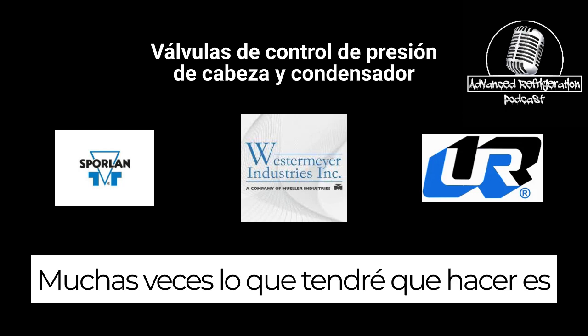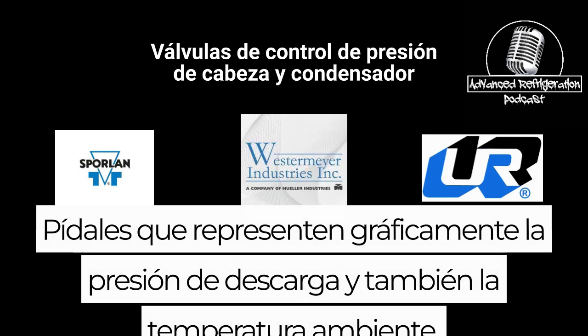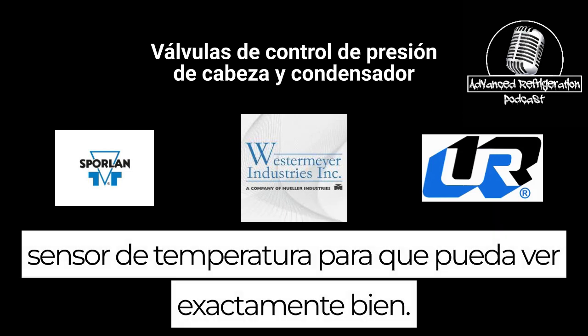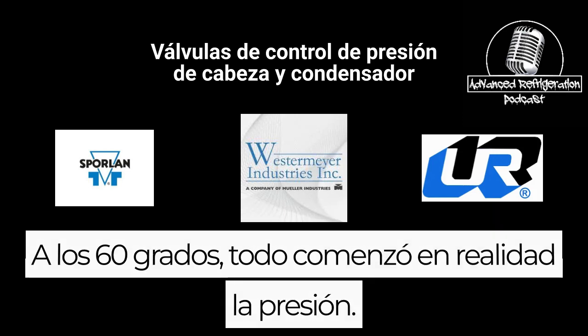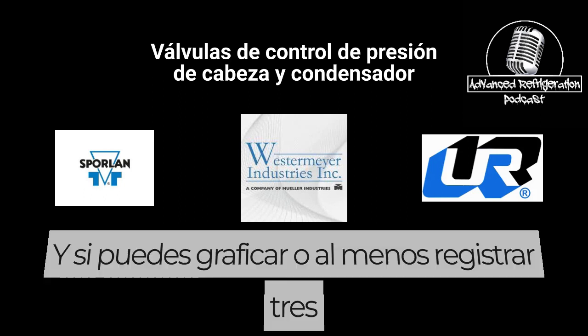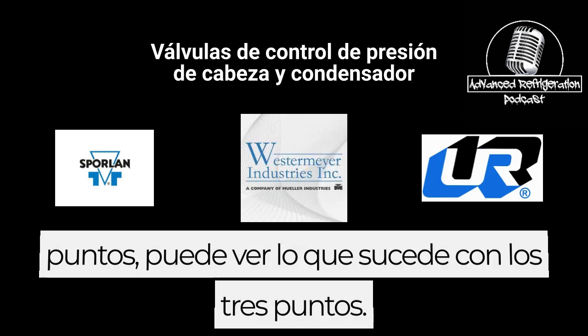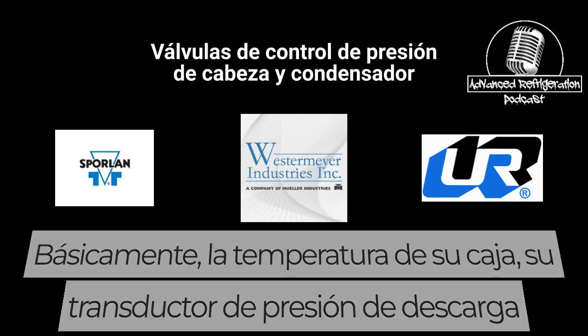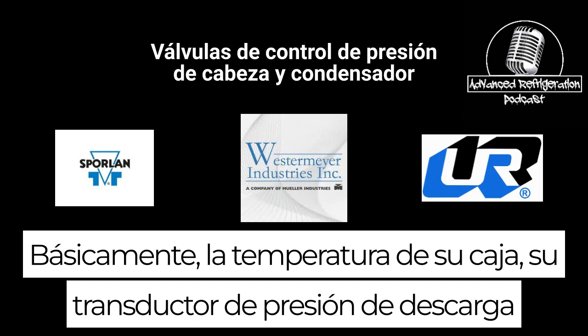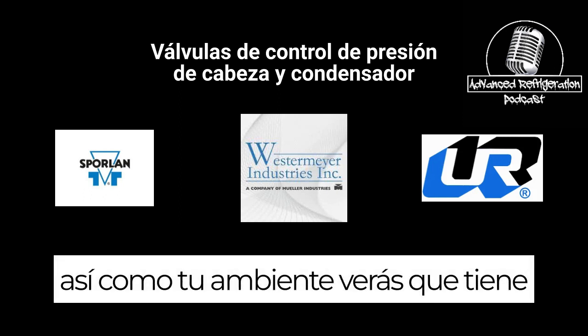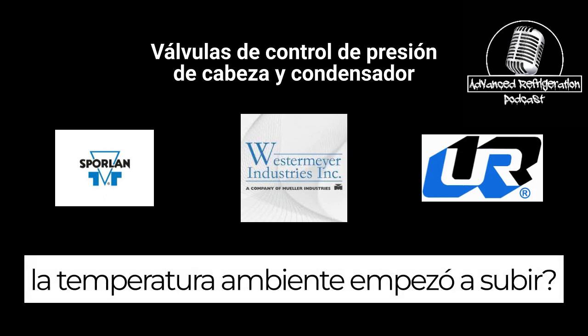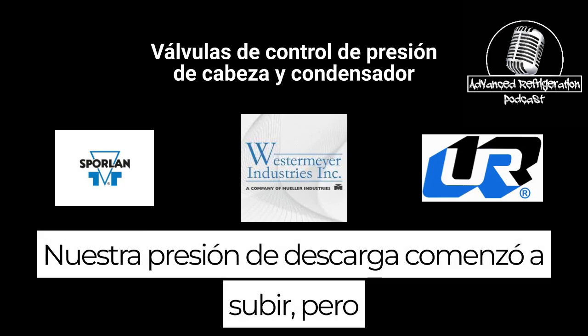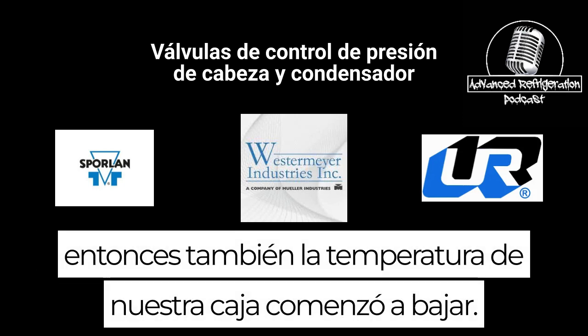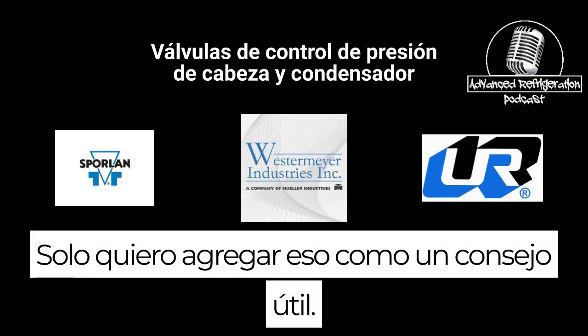A lot of times what I'll have guys do is graph the discharge pressure and then also the ambient temperature sensor. So you can see exactly, okay, at 60 degrees, everything started actually running the pressure it should have. And if you can graph or at least log 3 points, you can see what's happening with all 3 points. Basically your case temperature, your discharge pressure transducer, as well as your ambient. You'll see as the ambient temperature started to go up, our discharge pressure started to go up, but then also our case temperature started going down. I just want to add that as a helpful tip.